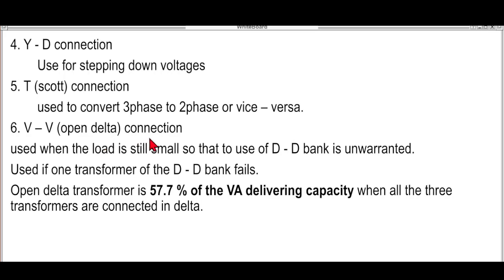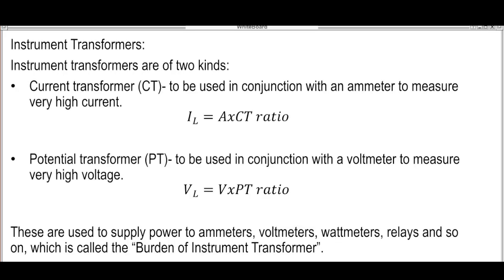Then the open delta is the V-V. Meaning, we have two transformers which are wired to have a three-phase output. The open delta transformer has only 57.7% of the rated kVA capacity compared to the three transformers that we use to form a delta-to-delta connection of a three-phase transformer.